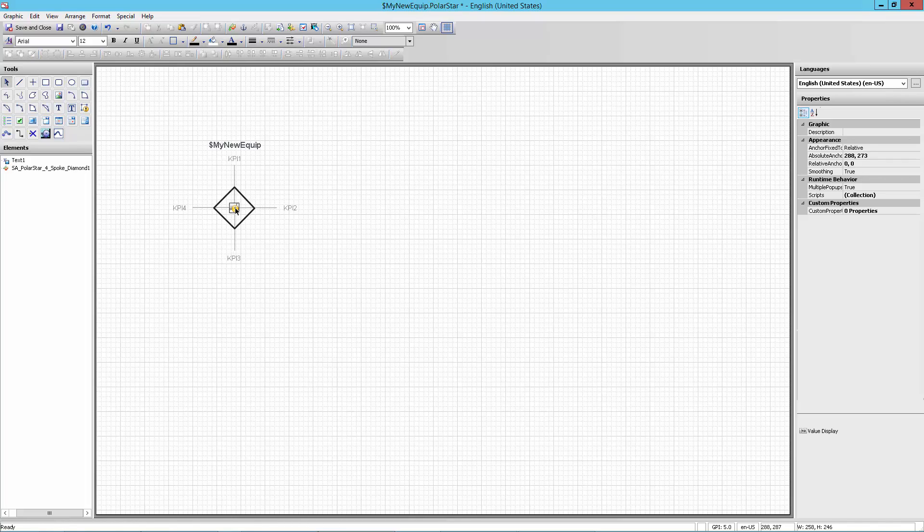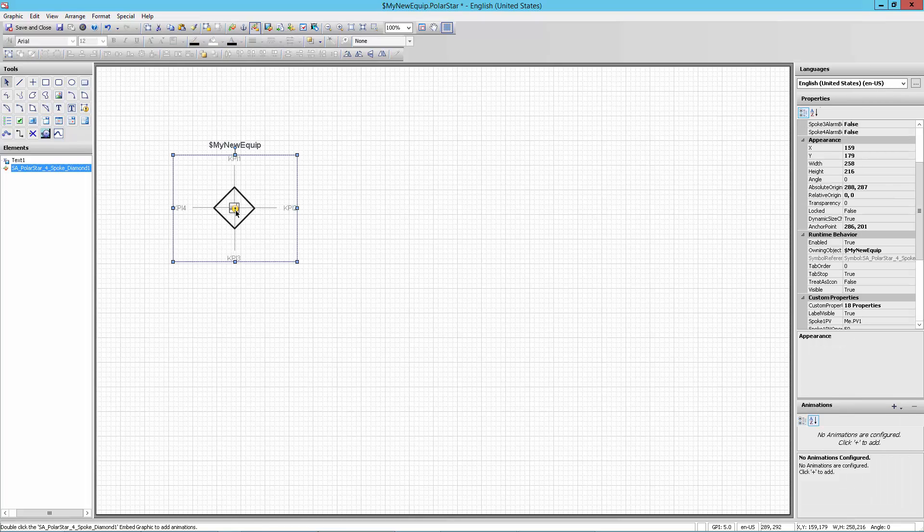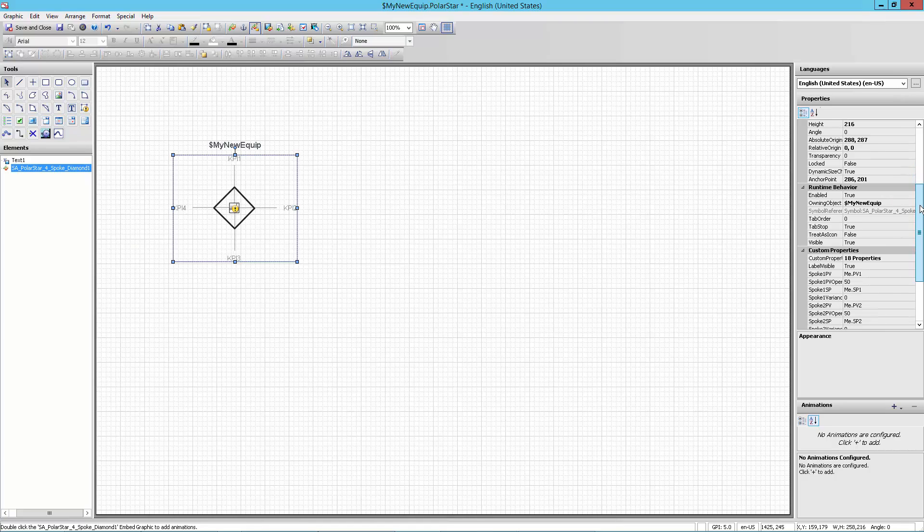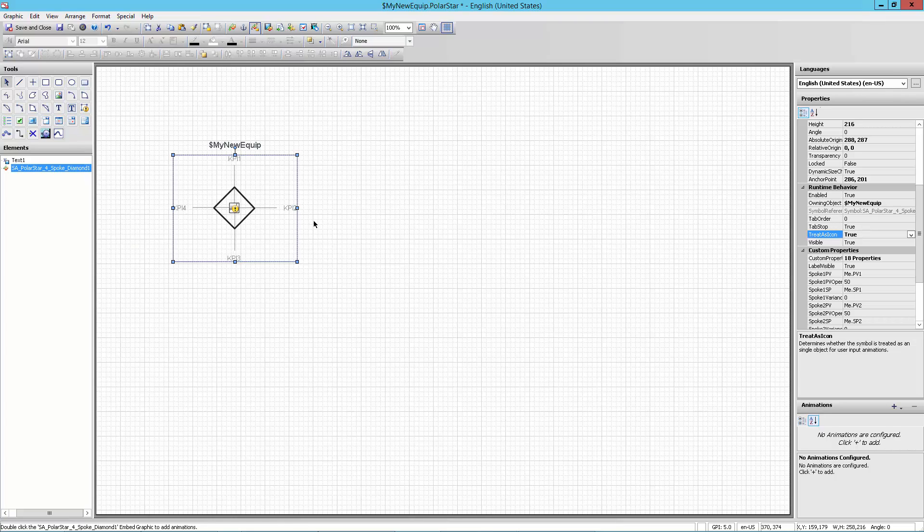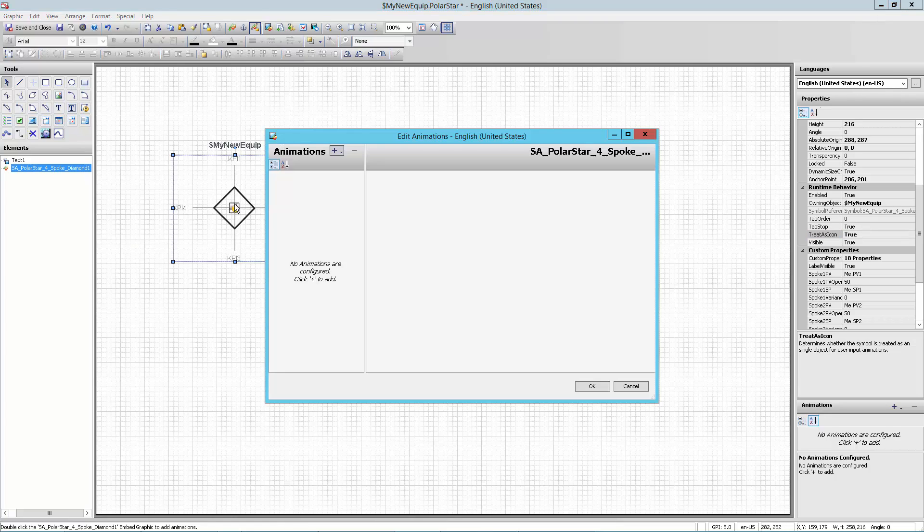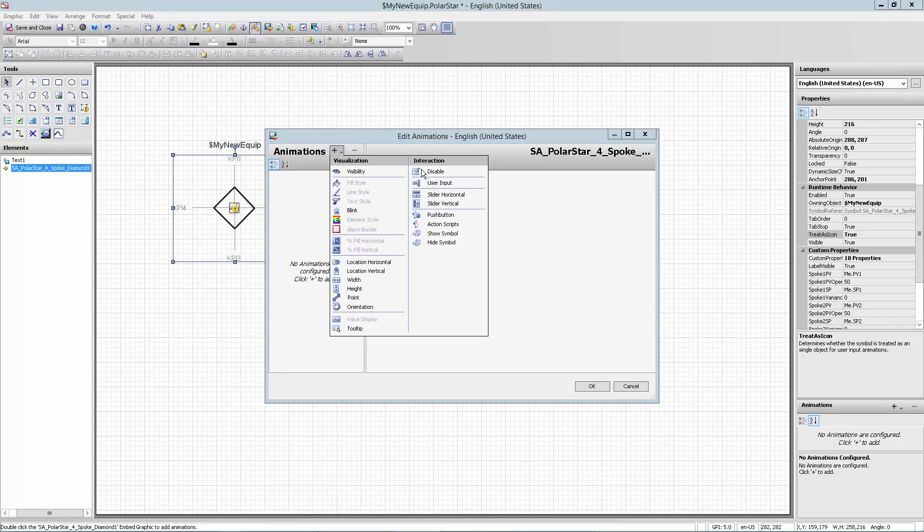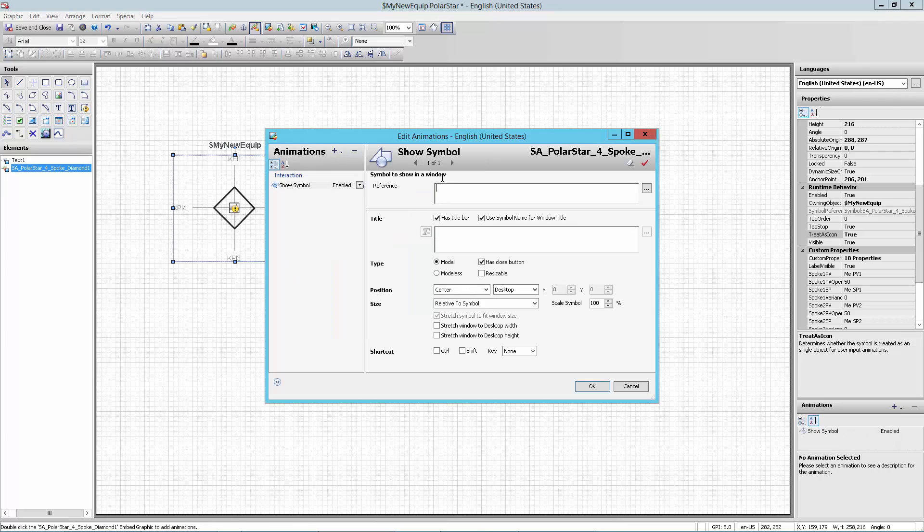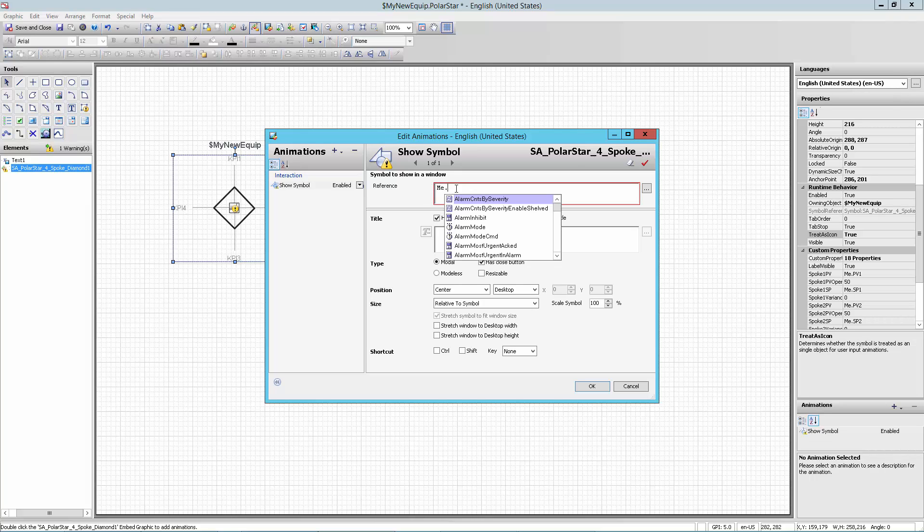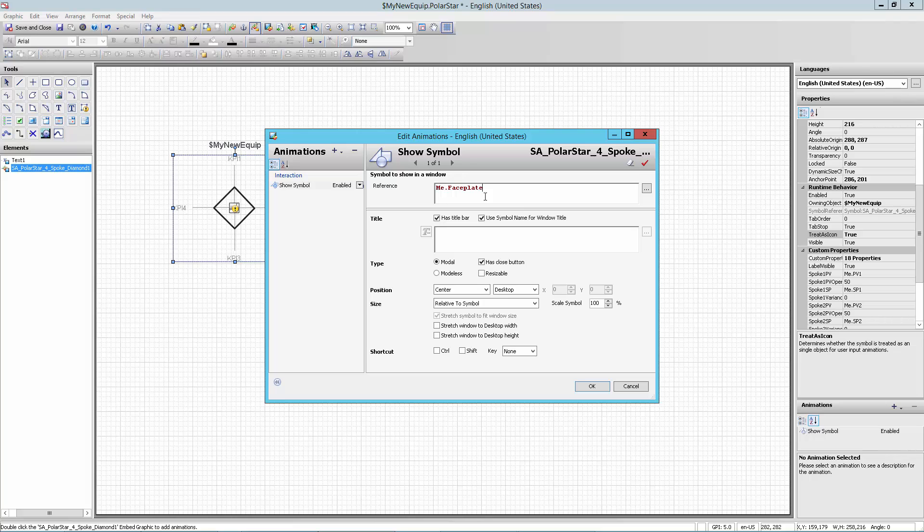I just need to link it to the faceplate. So what I'm going to do is come over here to the symbol attributes and turn this treat as icon on. What this does is that if there were any in this base symbol, if there were any animations that would accept a click or a touch, by turning this treat as icon on, what I do is I say this is going to now happen at the top symbol level. So now that when I come in and double click and add an animation, I can add these interactive animations. Before I hit treat as icon as true, these interactive animations would have been disabled. So I'm going to add show symbol. And in this particular case, I'll just go ahead in the reference and type me. Me is a relative reference. So I'm looking for a faceplate on me. I'll hit the F and then faceplate comes up. I'll click in there. So I have gotten that done.